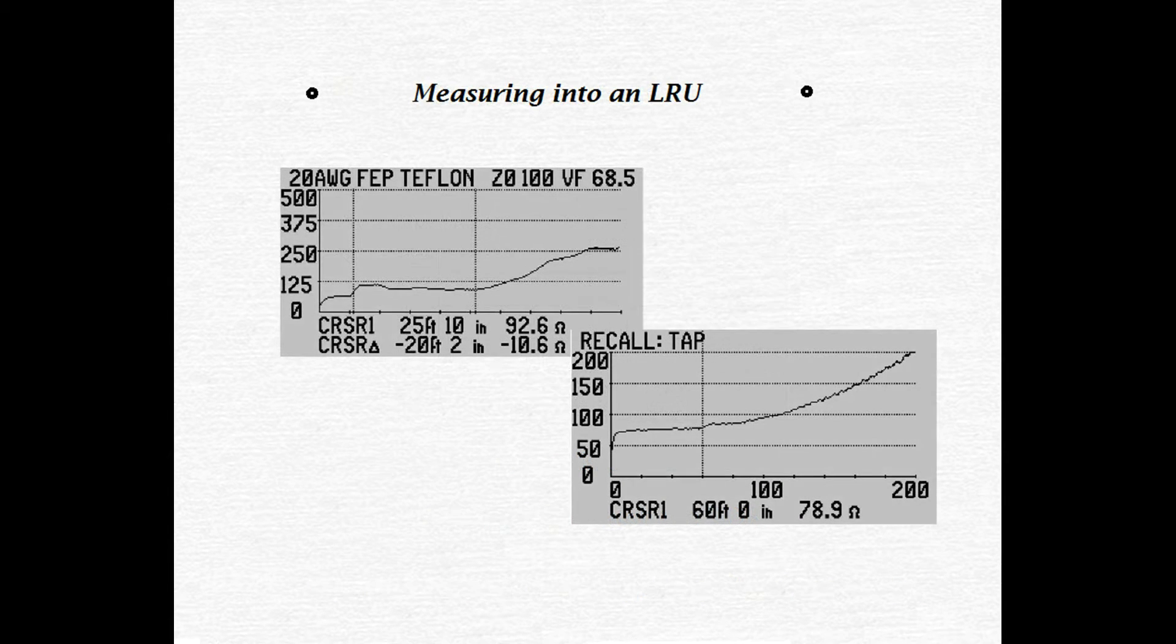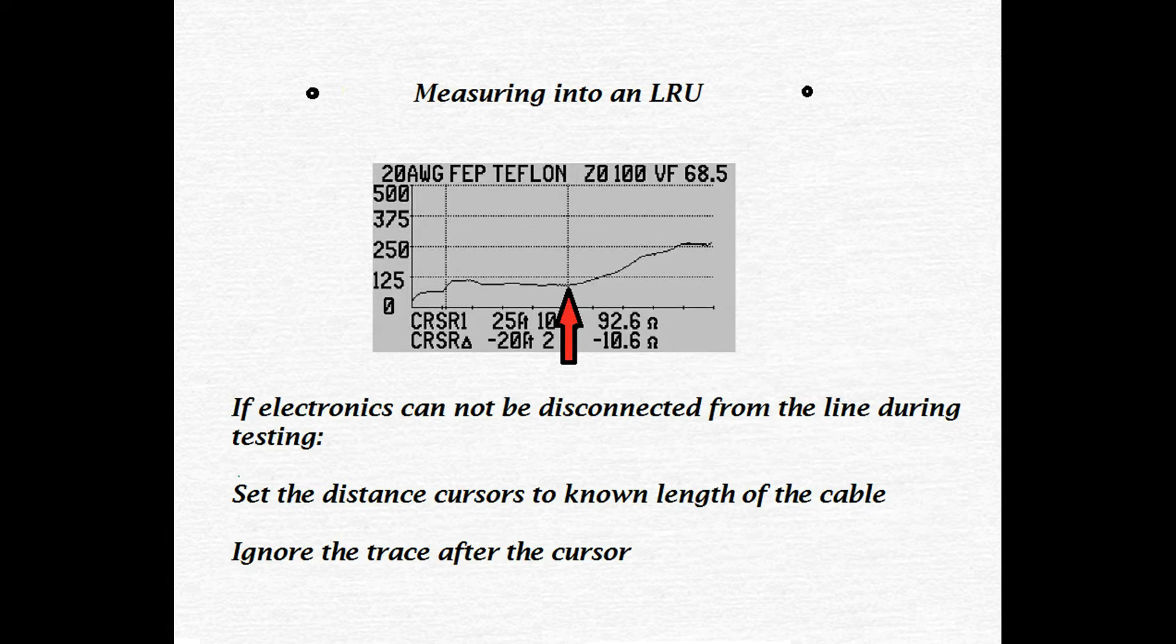I've mentioned it before, but here's a workaround. Try not to transmit into an impedance matching device, or an LRU. However, if there's no way around it and you have to transmit into an LRU, do some research and find out the length of the cable you're testing. Then set the cursor to the known length of the cable. From this point on, ignore anything on the trace after your cursor.